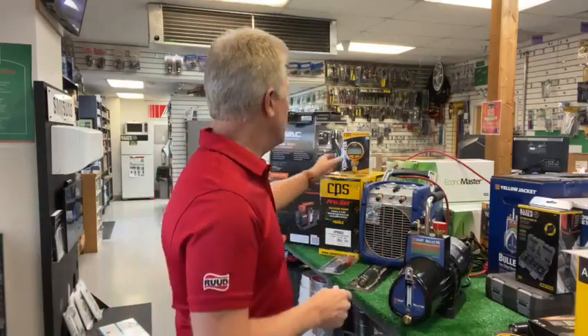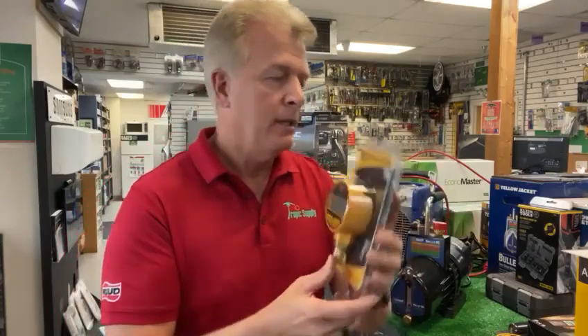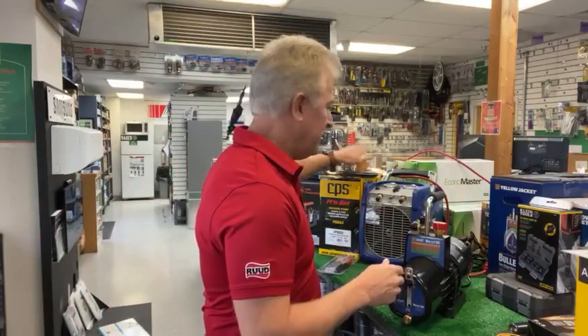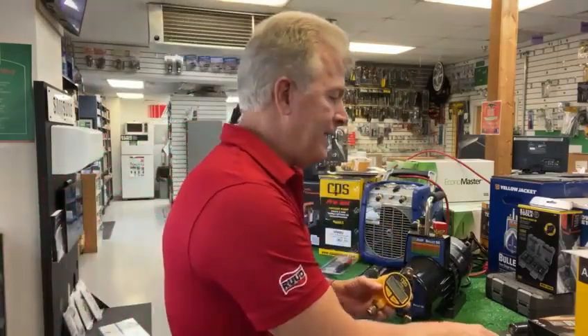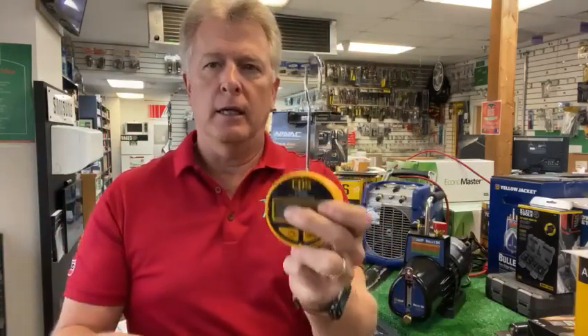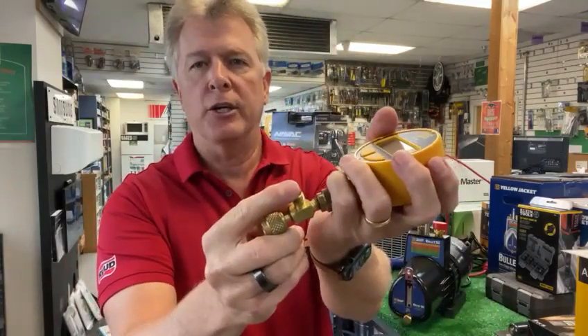Today what we're going to be going over is a tried and true micron gauge from CPS. This is the VG200 electronic vacuum gauge from CPS. I've been using this in the field for about eight years now. In fact, we're not going to open that package because I've got mine here that we'll show you. It's a nice little unit — it comes with the gauge, a carrying case, a hook clip, and an access T so that you can connect that to the unit and connect the micron gauge in your hose.